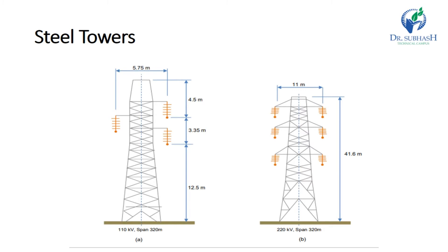Steel towers may be used for long distance transmission and higher voltage. Steel towers have greater mechanical strength, longer life, and can withstand stronger climate conditions. We see in the figure a single circuit tower and a double circuit tower. A double circuit tower has a moderate additional cost to build as a single circuit tower, and it has the advantage of continuity of supply. In case of a breakdown on one circuit, the continuity of supply can be maintained by the other circuit.